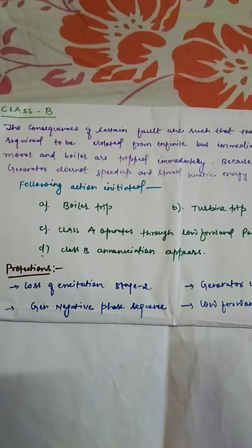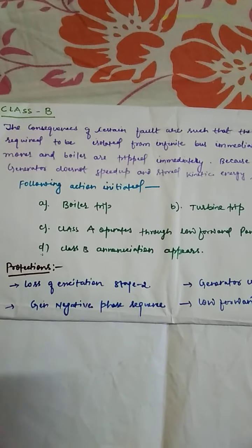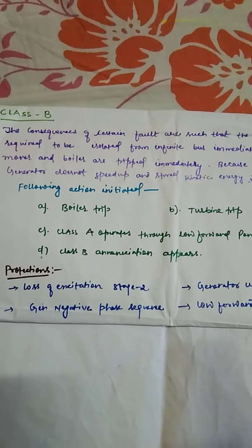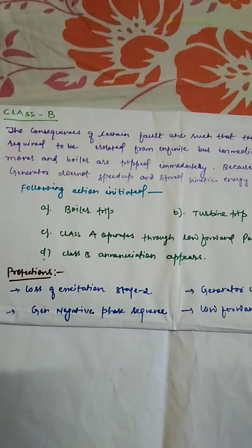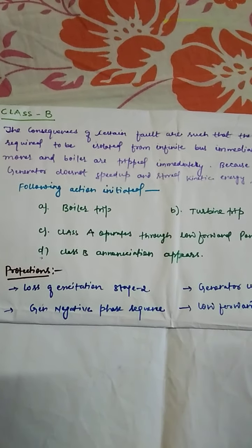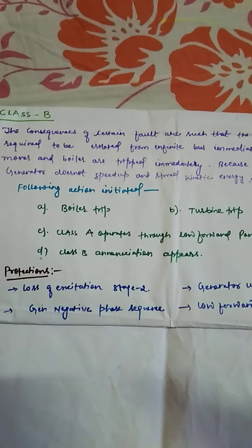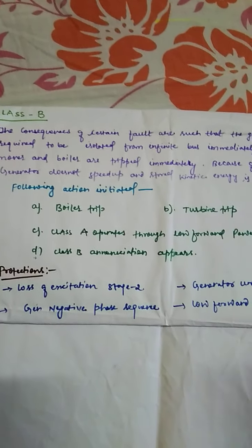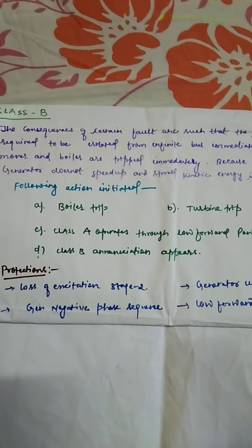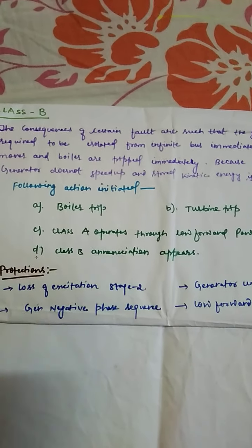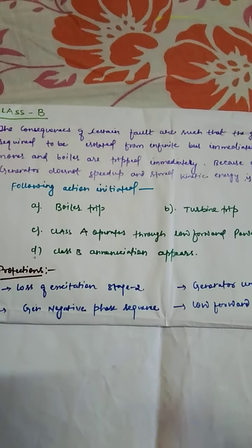So it is not required to immediately isolate the generators, since there is no fault inside the generators. Just because of the turbines and boilers, we isolate the generator after some time, because even if the boiler or turbine trips, we have kinetic energy. So that kinetic energy is being utilized by our generator.